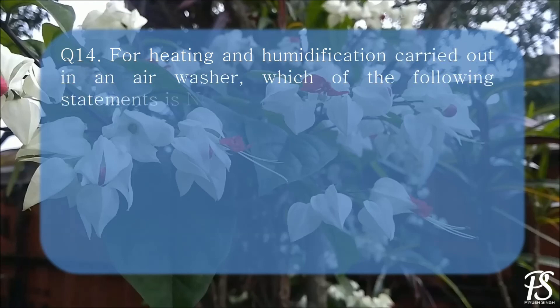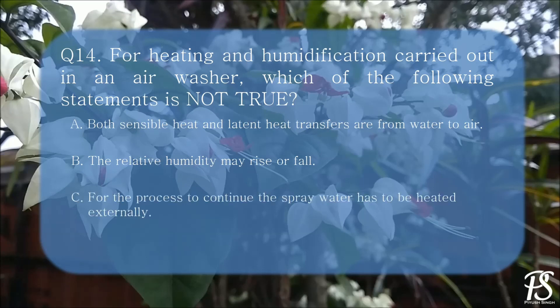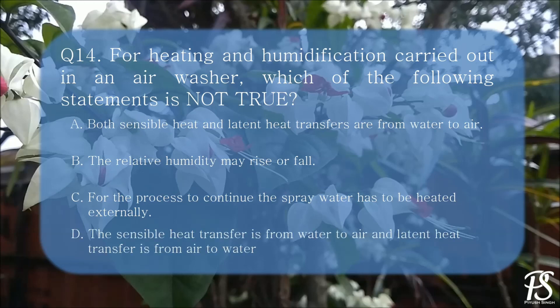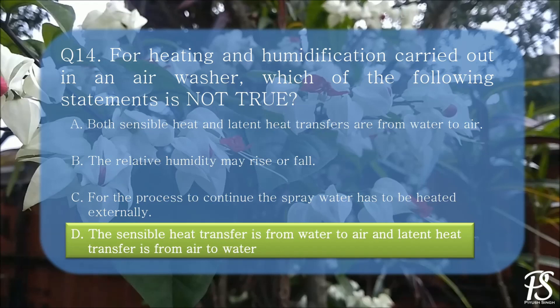For heating and humidification carried out in an air washer, which of the following statements is NOT true? A. Both sensible heat and latent heat transfers are from water to air. B. The relative humidity may rise or fall. C. For the process to continue, the spray water has to be heated externally. D. The sensible heat transfer is from water to air and latent heat transfer is from air to water. Statement B is correct — relative humidity may rise or fall. Under this condition, both sensible heat and latent heat transfers are from water to air, causing a drop in enthalpy of the water, which must be externally heated. Hence A and C are correct. The answer is D — that statement is false.